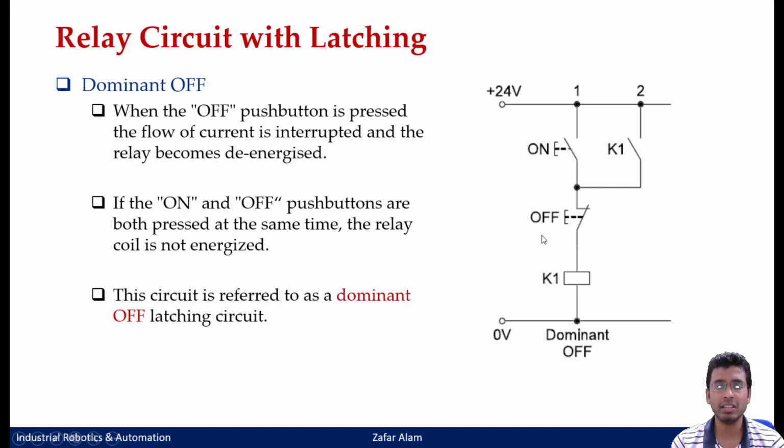So basically, by latching, I am trying to convert this push button actuation into a switch, right? Earlier, when I pressed this push button on, my relay got actuated only as long as the on push button was pressed. The moment that on push button was released, my relay got de-energized.